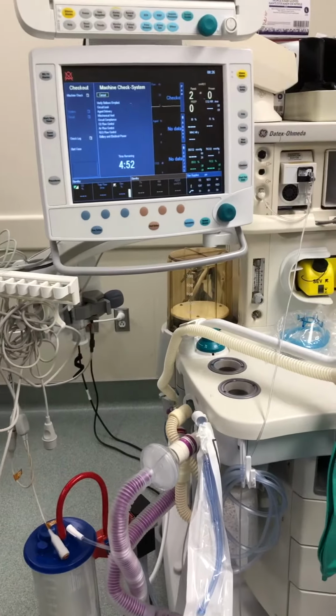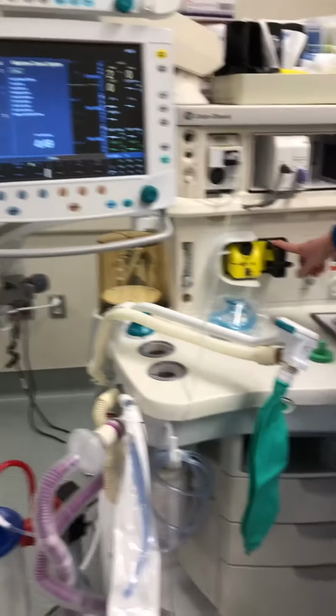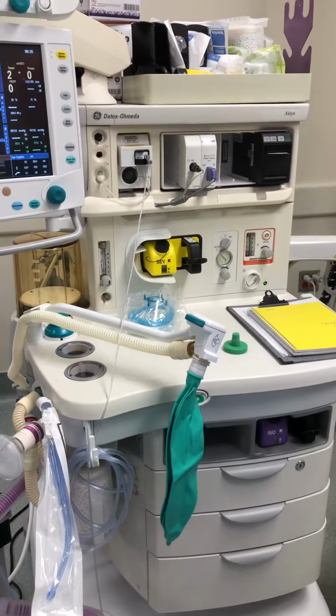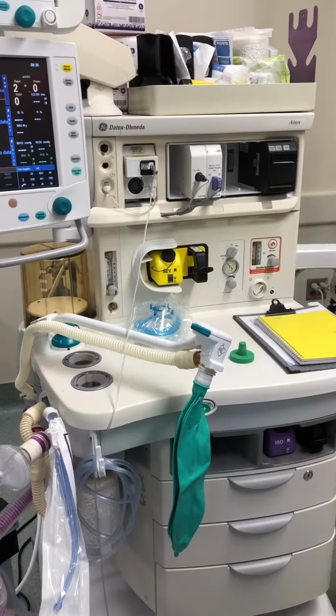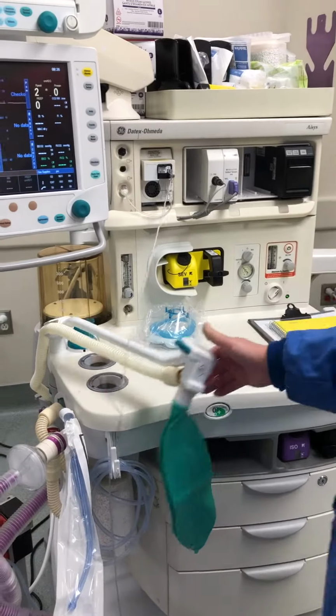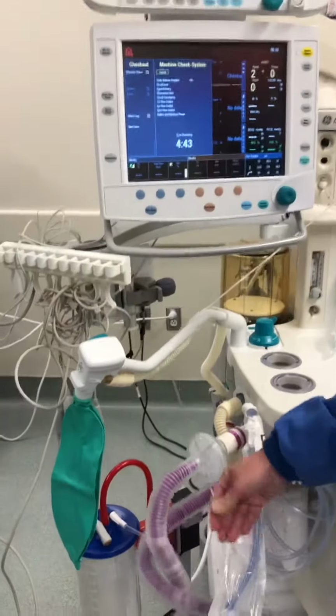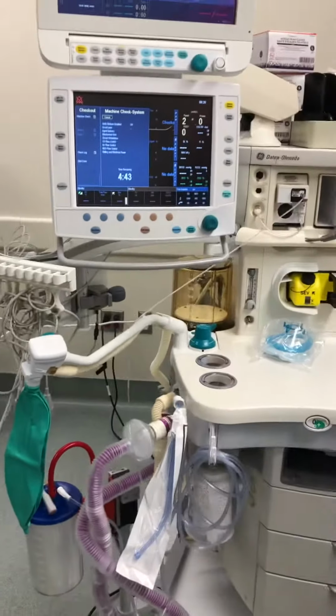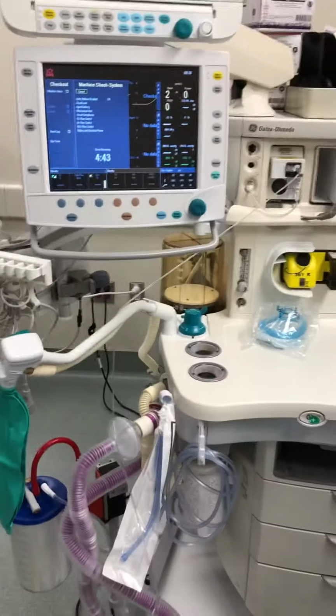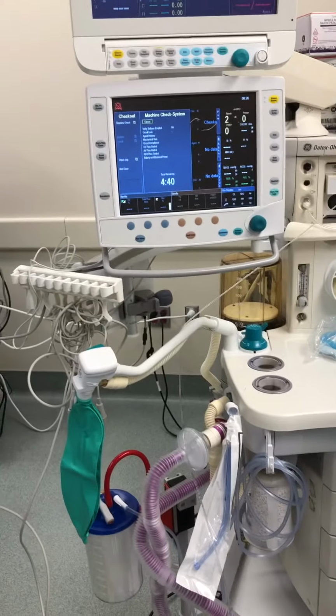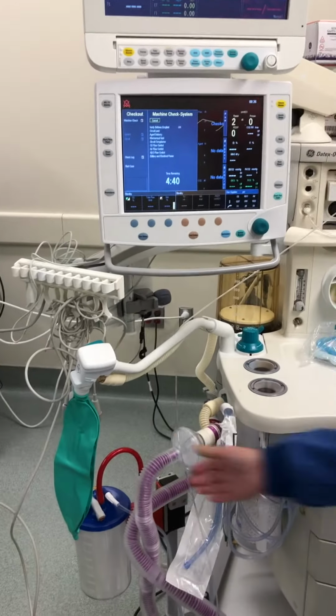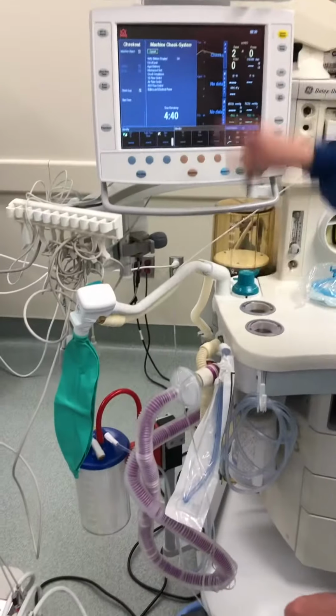So this is 5 minutes. You want to make sure that there's a cassette installed into the active bay, which 99% of the time there is. And now it's going to do the circuit leak. It's on the ventilator side right now because our bag to vent switch is on vent. With that circuit leak, if it's under 100, it's going to say okay, less than 100 mL per minute. And I can see the waveform dropping.